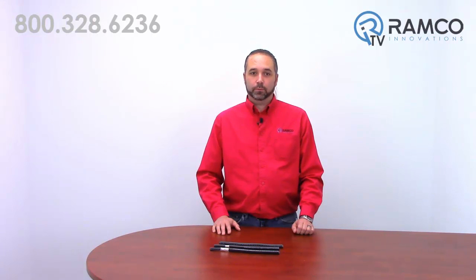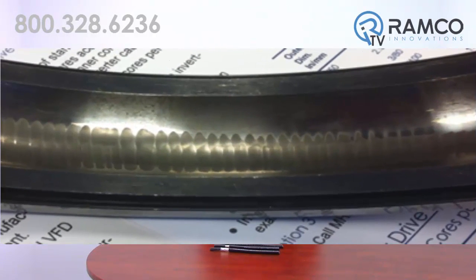When there is common mode voltage, current will flow to ground, possibly through the motor shaft via the motor bearings. This will lead to bearing pitting and premature failure.